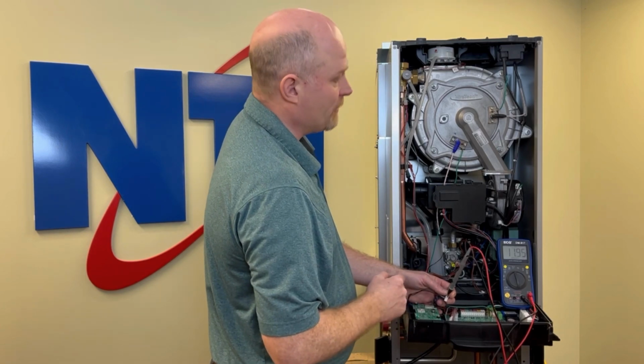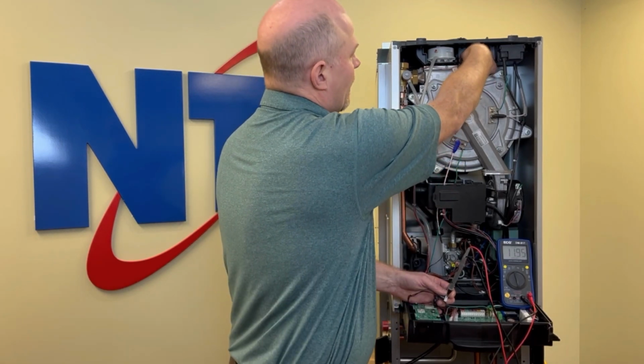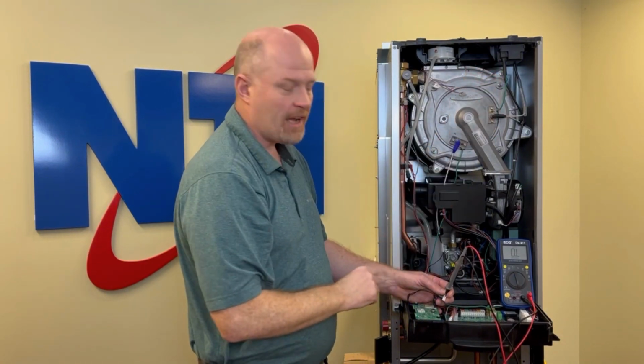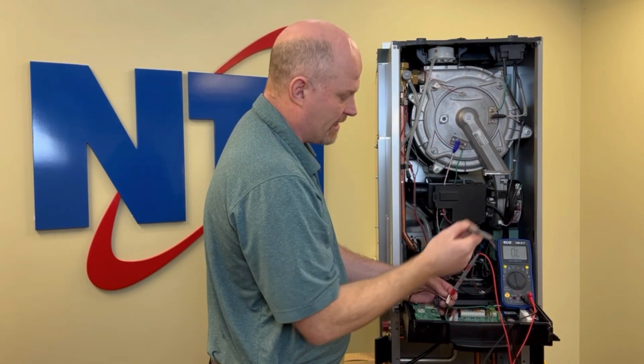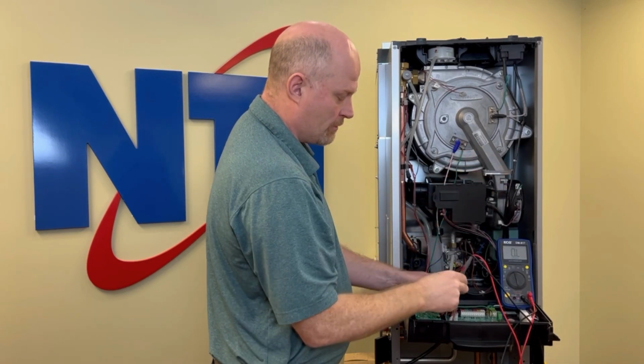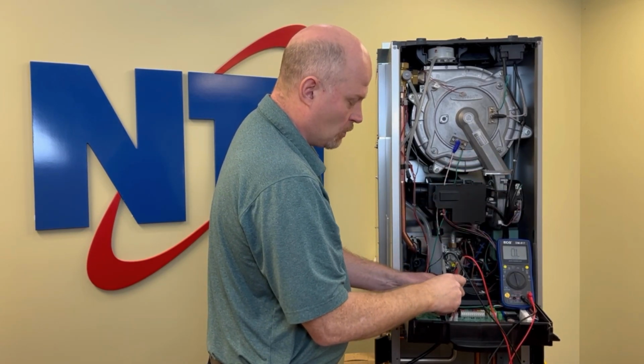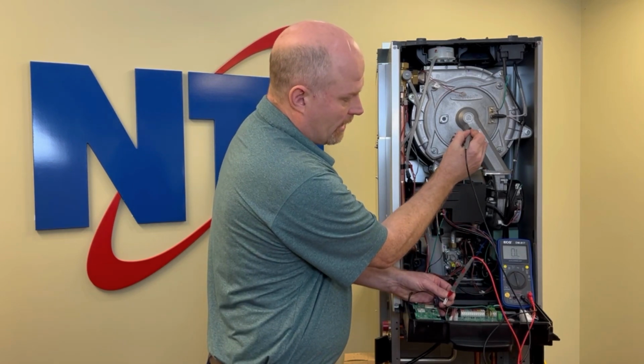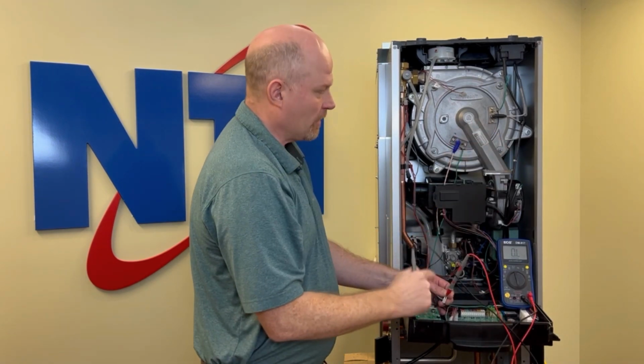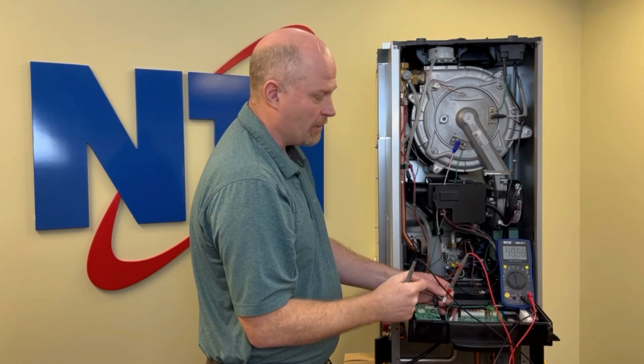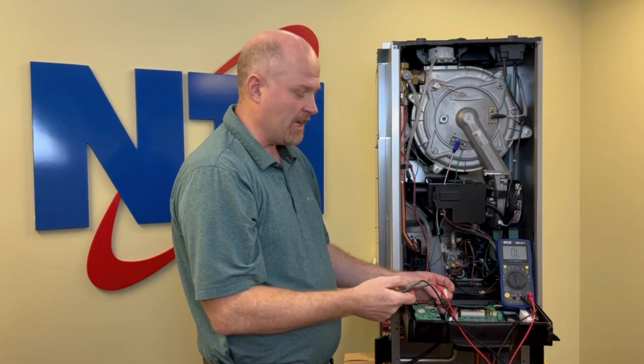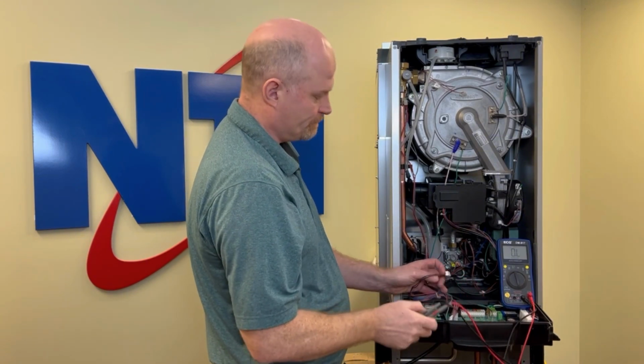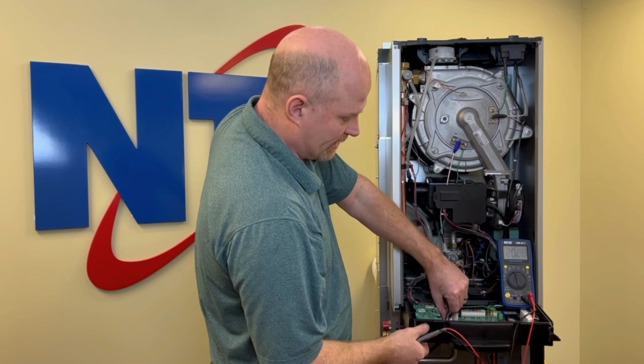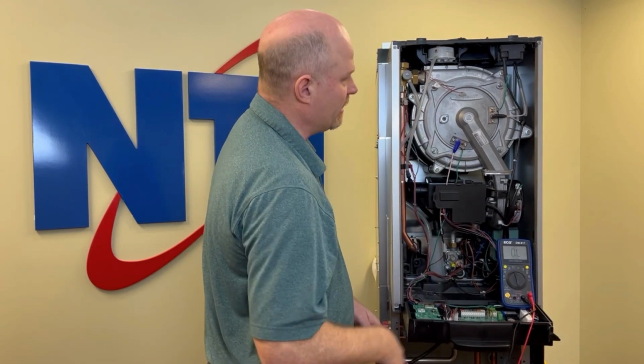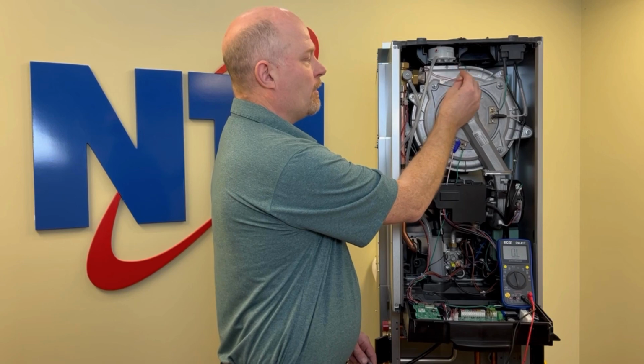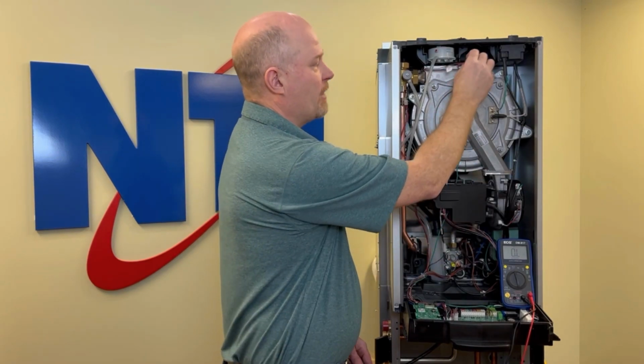Another check you can do to see if it's the wires or the sensor is to disconnect this harness, and you should have a completely open circuit. You can then test from each wire to ground and verify that you have no resistance or no continuity at all, which would indicate, again, if you had a continuous contact between, for example, ground and one of these wires, it would indicate that you have a damaged harness and would need to replace this harness. Once you verify that the sensor is working correctly, the combustion chamber is clean, you can either replace the sensor or wire harness as needed, or fix the problem with the air and reassemble your boiler.